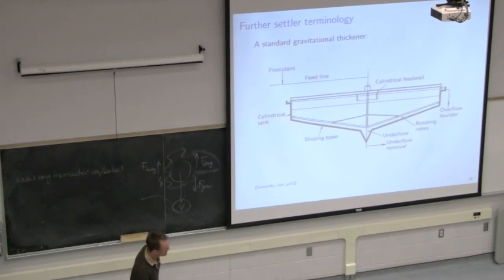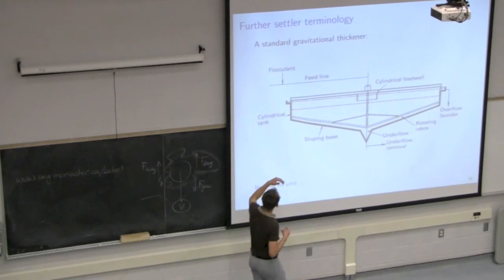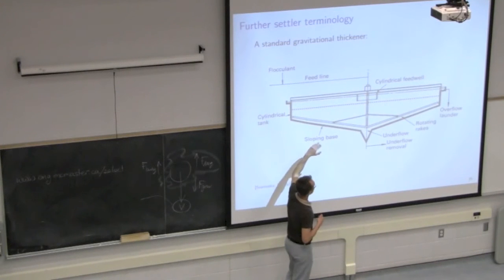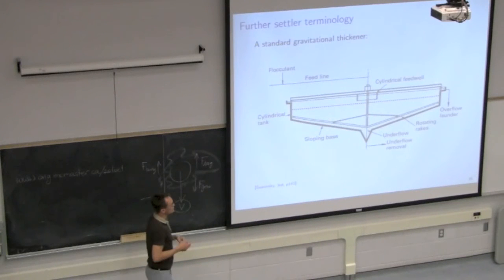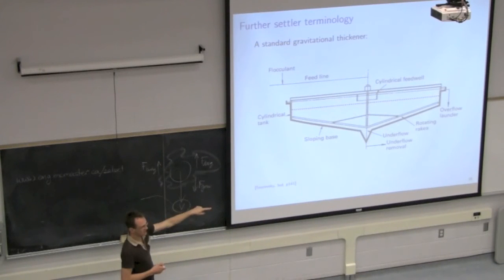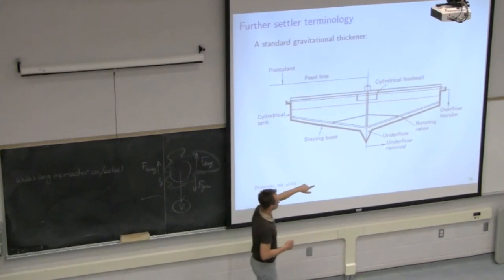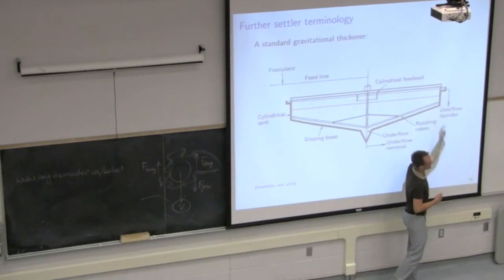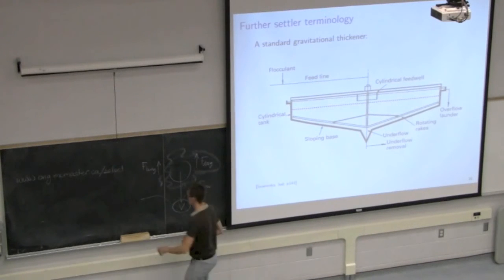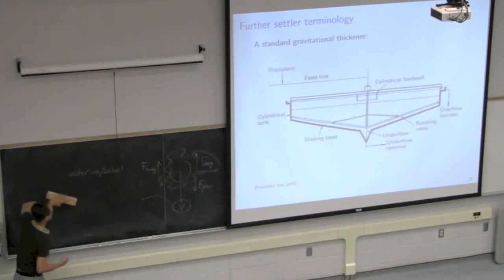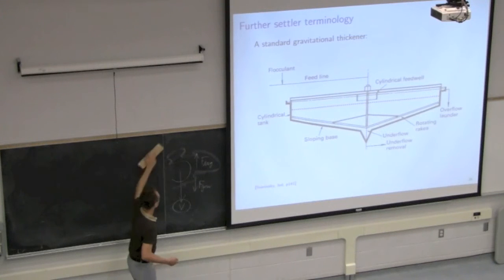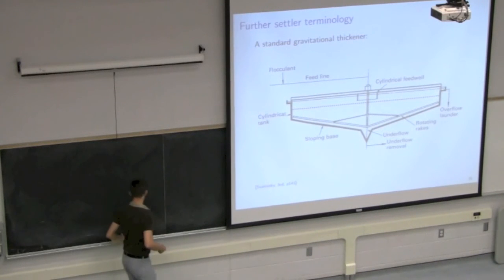Where we're going in this next section is looking at the preliminary design of a sedimentation vessel. One thing I want to stress again is that this unit operates at steady state. So the solids coming in at the feed point will almost all leave again in the underflow, in the sludge. We'll have almost no solids leaving in the overflow. The overflow is a pretty clear stream. So the separation factor on these units is pretty close to infinity if we're doing a good job of separating out.